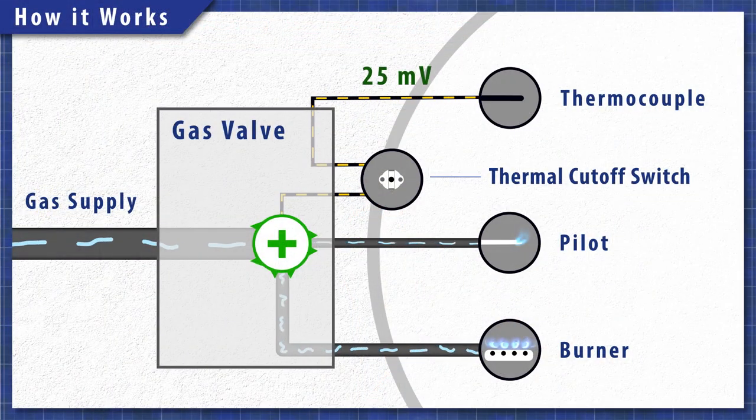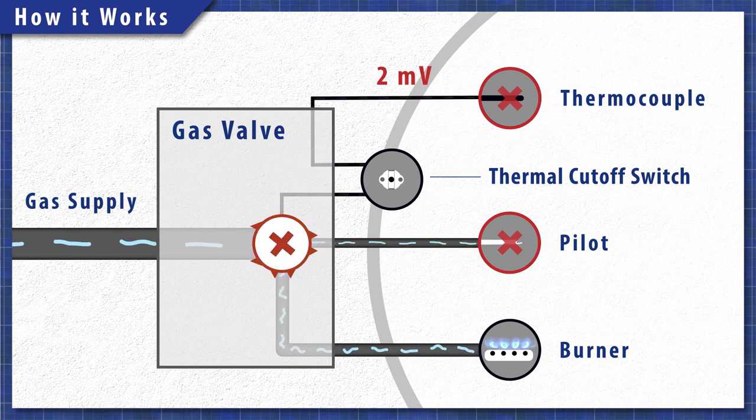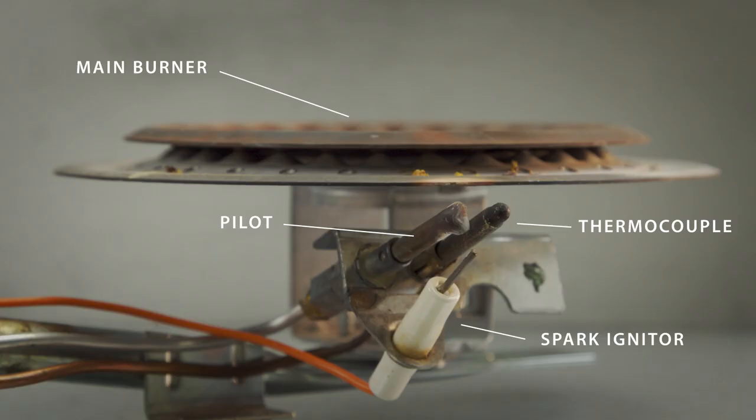The thermocouple also acts as a safety switch. If the pilot light goes out, then the thermocouple will cool down, the voltage will drop, and the gas valve will shut off. This prevents unburnt gas from being released into your home. Now if the thermocouple is faulty, then it will also prevent the pilot from staying lit.